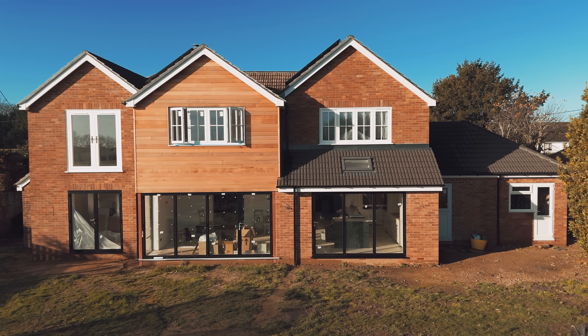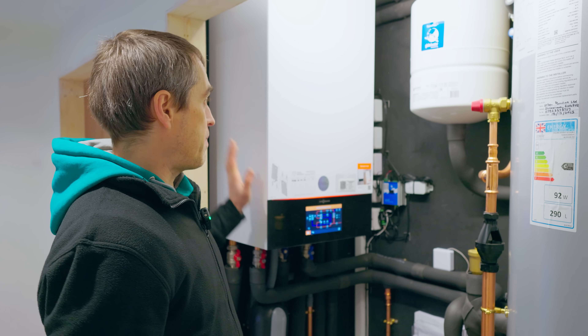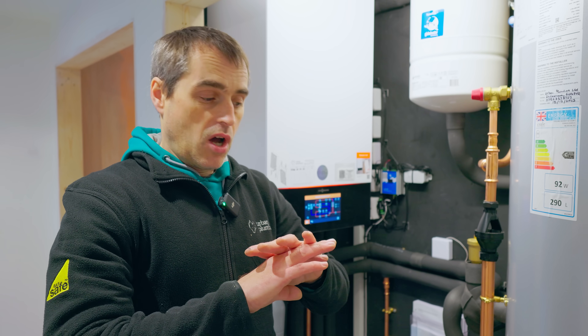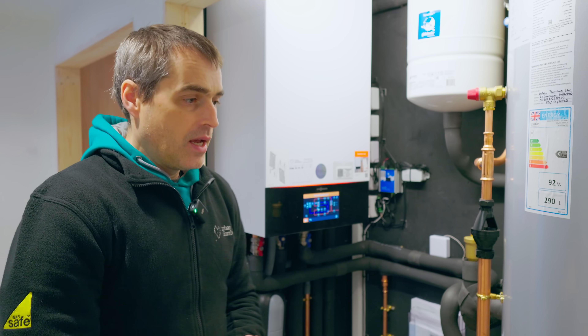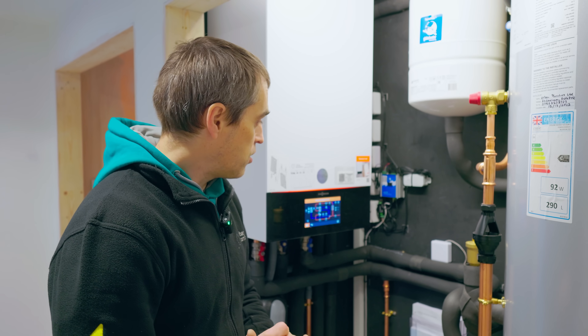So here we have another five-bedroom large property with a really simple system. I know some of you might think there's lots of pipework and cylinders — but you would have a cylinder in any case on a large property, and if you don't have a heat pump you have a boiler of similar size, and everything else is the same. Compared to most systems people would put in large properties, this doesn't have any thermostats, no zoning, no actuators for underfloor heating, nothing. It literally has flow and return from the heat pump to the unit, and flow and return to the heating. That is all. Fully weather compensated and controlled only by the external temperature and a heat curve on this unit. You can't get those systems simpler than this, and you also have monitoring — you can go to the link below and check the performance of this system as well.